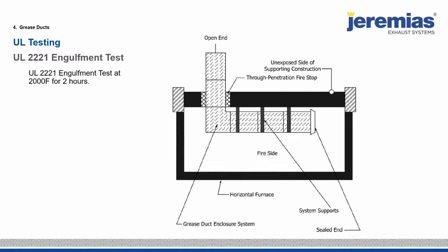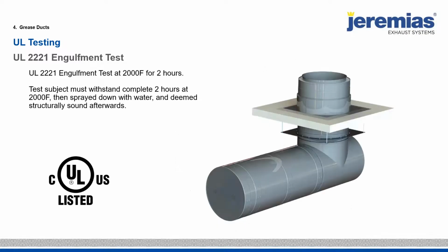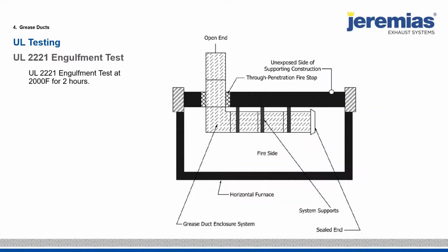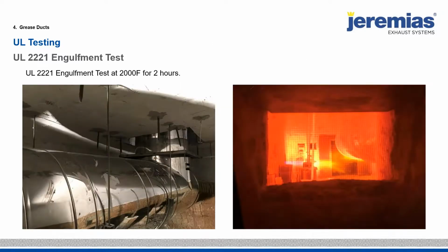Now, a second test I want to talk about is the UL engulfment test. This test is for 2 hours, for the 2-hour fire rating. What we have is a similar test subject right here, and you're placing the subject inside an oven, so you're heating the outside. The fire side is on the outside of the ductwork. And what you're really doing also is testing the through penetration fire stops to make sure it's containing the heat as well. Now there's 2 of these ovens in North America. One's in Chicago, that's where we're looking at for the UL laboratories. The second is in Houston, Texas, which is the Intertek ETL labs.